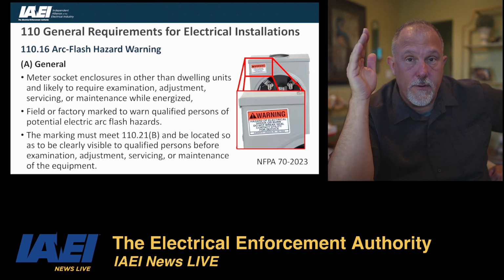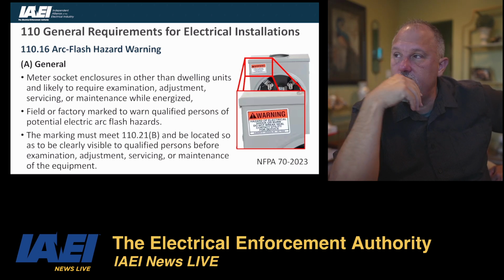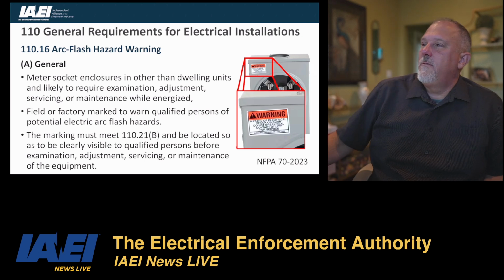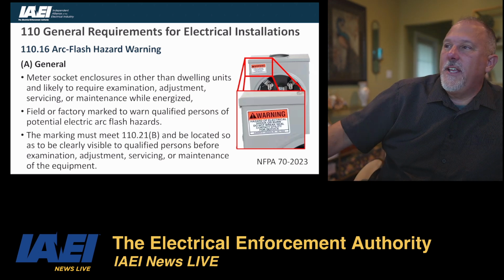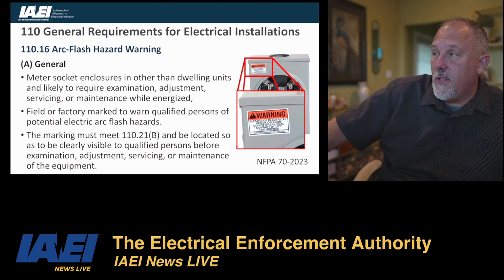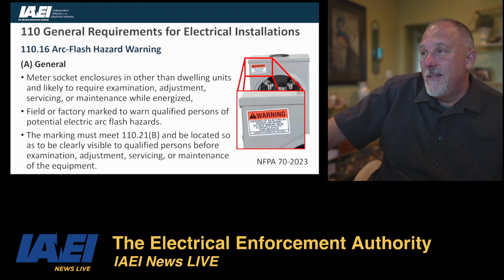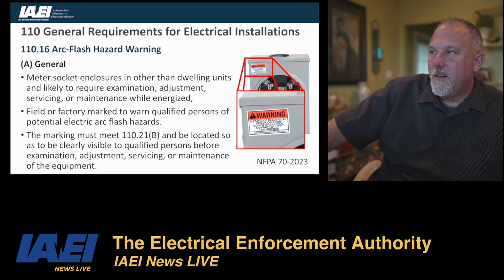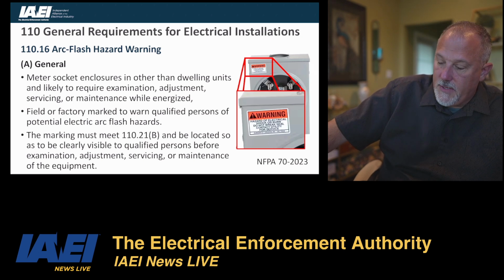You're not labeling the breaker itself. You're labeling the enclosure within which the circuit breaker is installed. I don't like the way that's written. It says the necessary equipment, which consists of a circuit breaker or a switch and fuse, and their accessories. Service equipment is not a circuit breaker. It's the equipment within which, every time I see something like this, I just go crazy with, it doesn't make sense. The language, well, you know what we're talking about. It's the enclosure, not the circuit breaker.